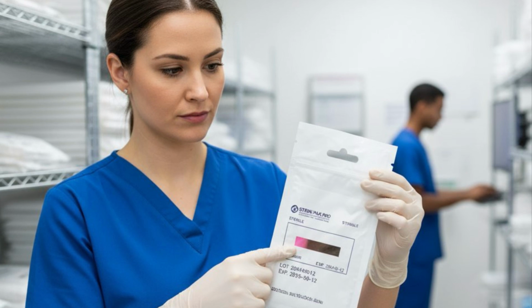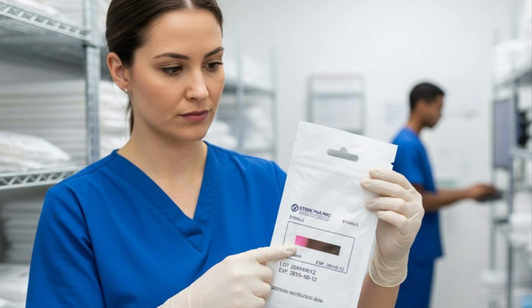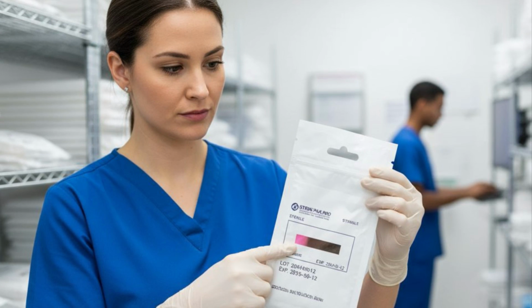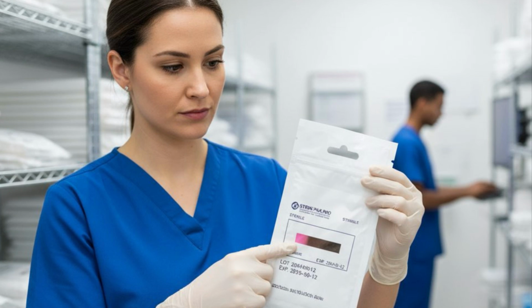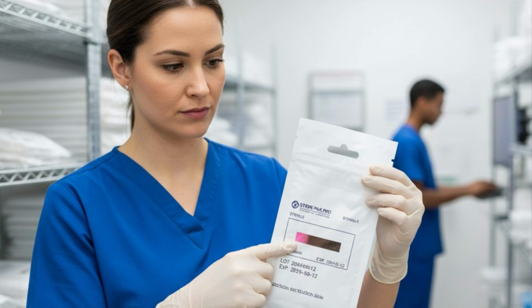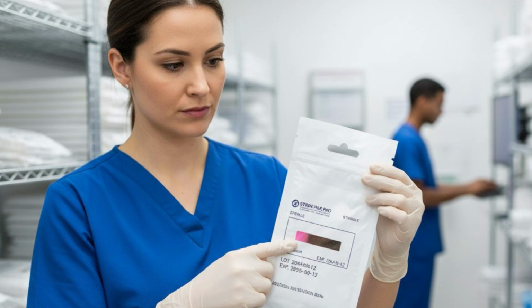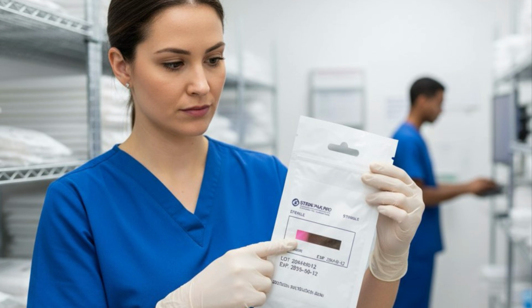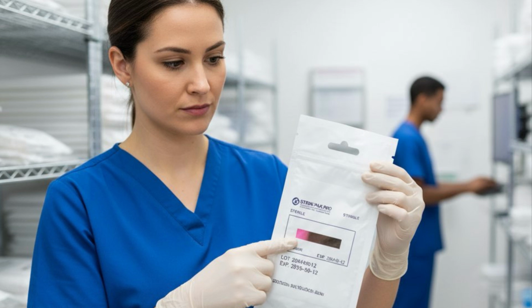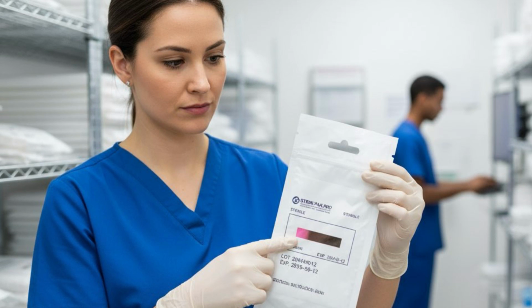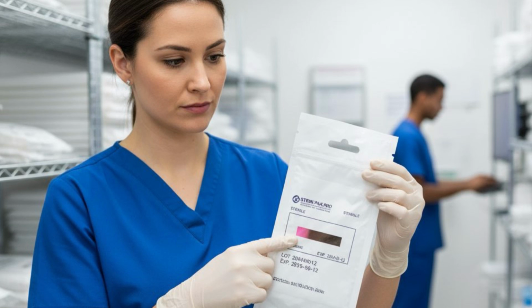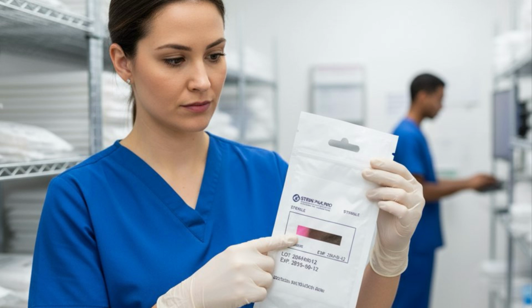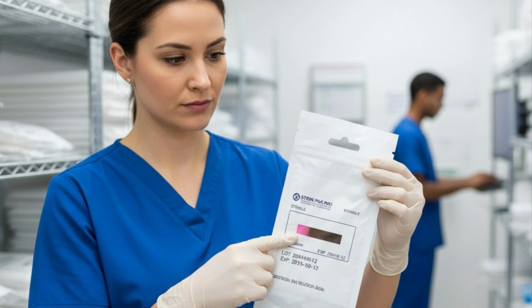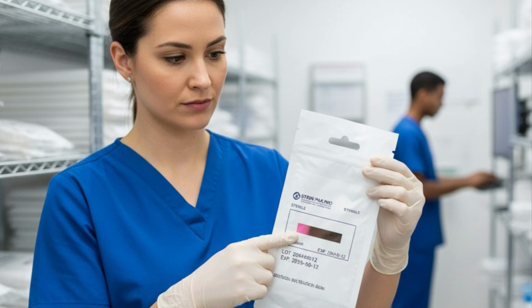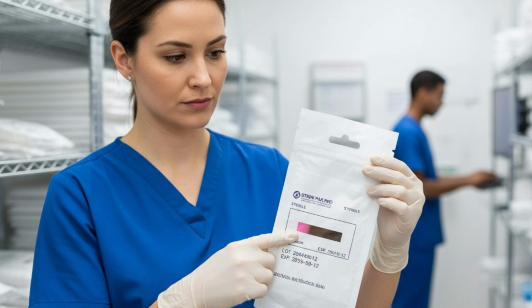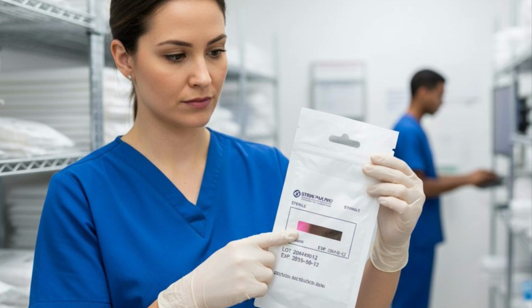To ensure that sterilization has been effective, hospitals use a multi-layered approach to quality control. Biological indicators, which contain highly resistant bacterial spores, are the gold standard. If the spores are killed after the cycle, it confirms that the sterilization process was successful. Chemical indicators provide a quick visual check that the item has been exposed to the sterilant, but they do not confirm that the microbes have been killed. Finally, physical monitoring of the sterilizer's temperature, pressure, and time provides a record of the cycle parameters.